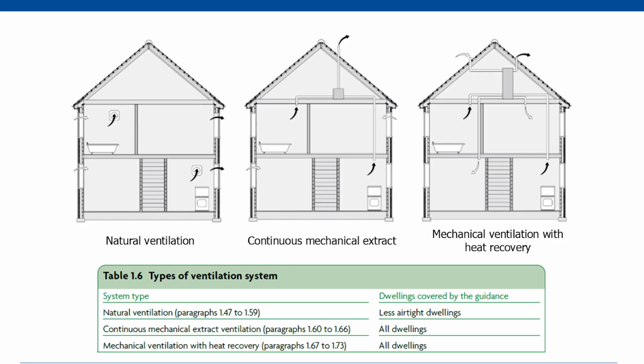In the middle, we have continuous mechanical extract ventilation, previously known as System 3, or MEV. That's a centralised version on the drawing, so one unit ducts off to various different areas. And finally on the right, we have mechanical ventilation with heat recovery, previously known as System 4, continuous mechanical supply and extract with heat recovery, MVHR. So there are the three prescribed ventilation system types, with passive stack being removed.